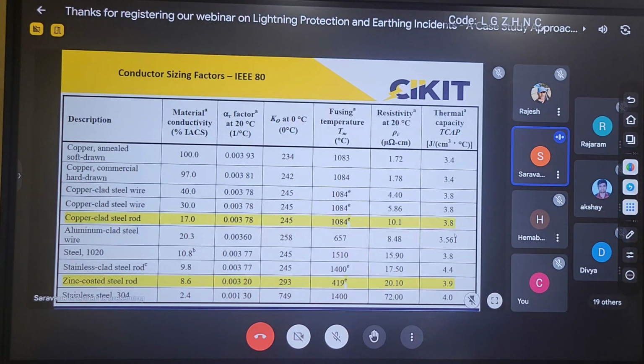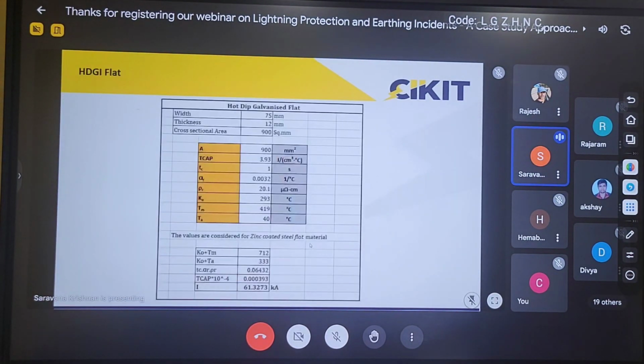The zinc coated steel rod is nothing but the parameter related to zinc coating, as in GI. Whenever we are performing the calculation, I have to calculate this. By using these parameters, if we perform the calculation, then the conductor sizing has to be 75/12. If I use 75/12 of GI, then only it can have a current carrying capacity of 61 kA. So if I want to replace this copper conductor with the GI strip, I cannot go for equal dimensions; 50/6 of copper cannot be replaced with 50/6 of GI strip. I have to replace the 50/6 copper strip with 75/12 mm GI strip. For replacing earthing conductors, the cross-section area should not be considered, whereas the current carrying capacity of the conductors should be considered.